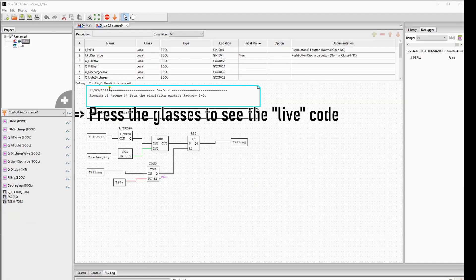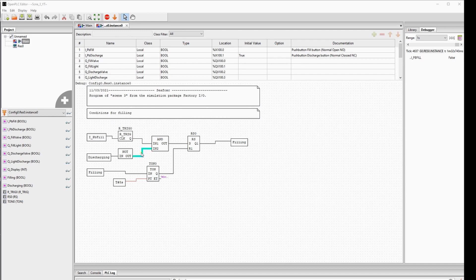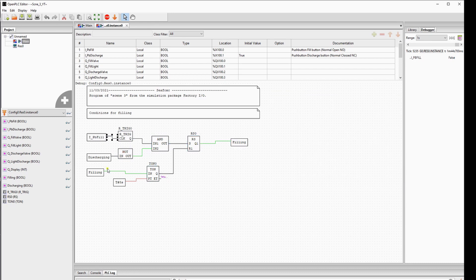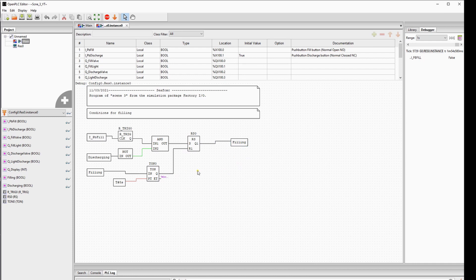We will simulate our logic for the filling conditions to see how it works. In the simulation, you will see already one connection of the AND port is true, because we are not discharging. We force the signal of the push button to true and back to false — the same as pressing it in Factory IO. The set block will activate filling and the timer will start. After 8 seconds the TON timer will reset the RESET SET function block. The variable filling will be false again and the timer will also stop.